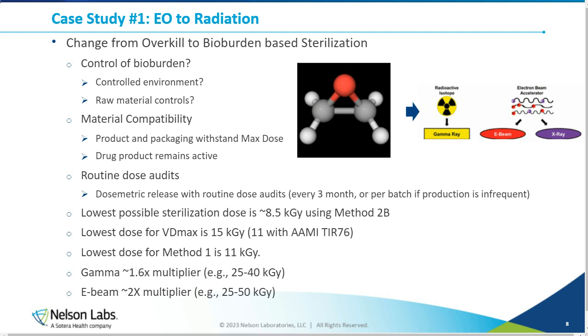And then for the other validation methods, such as VD Max, the lowest we're really going to get is 15 kilogray. There is a new AAMI TIR that has been published, AAMI TIR 76. It is an AAMI document, and the lowest that can get to is 11 kilogray. Method 1, the lowest dose we're going to get also is 11 kilogray. And some consideration with all of this is different modalities generally are going to have different dose ranges that the irradiator can hit. So just because I can get a low dose, such as 8.5 kilogray, that doesn't mean that's what my product is going to see. I'm going to see a range of doses.